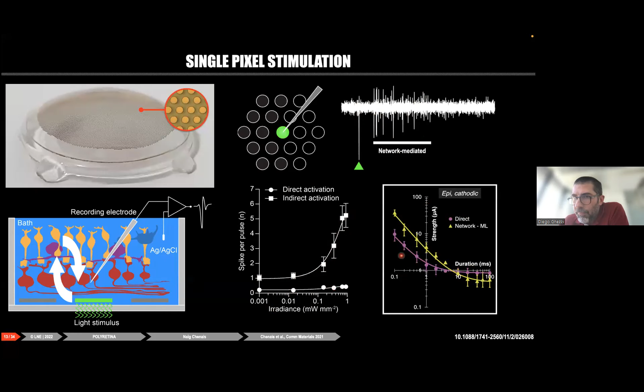You see that our device is very efficient, according to the irradiance, at activating the network-mediated mechanism, but not so much the direct activation of retinal ganglion cells. That comes down to an easy explanation. There is a combined explanation for it. One is represented here from an experiment made by the group of Daniel Palanker at Stanford, where he demonstrated that epiretinally, once the duration of the stimulus exceeds a certain threshold, the threshold being 8 milliseconds and ours being a 10 millisecond light pulse, network-mediated stimulation is favored compared to direct stimulation. So it's easier to generate spikes through the network than by direct stimulation of the retinal ganglion cells.